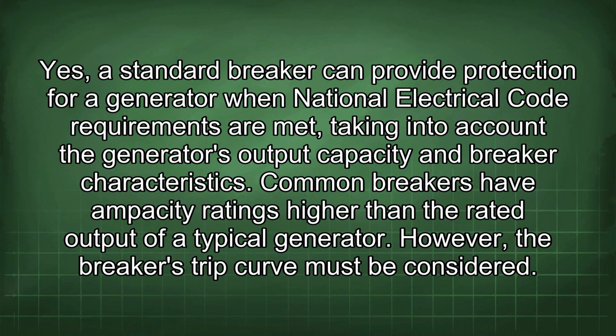Yes, a standard breaker can provide protection for a generator when National Electrical Code requirements are met, taking into account the generator's output capacity and breaker characteristics. Common breakers have ampacity ratings higher than the rated output of a typical generator. However, the breaker's trip curve must be considered.